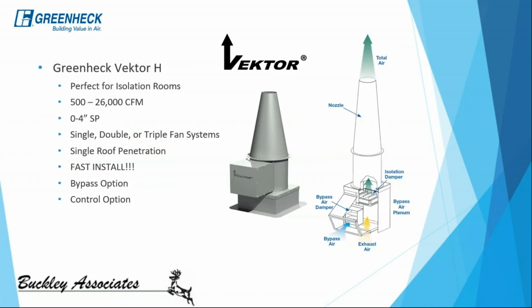So here's some quick information on our most commonly used laboratory exhaust fan. This is the Greenheck Vektor H. This fan is designed for anywhere between 500 and 26,000 CFM, and between 0 and 4 inches of static pressure. Up to 3 of these fans can be paired together into a single system, so we can put them all onto one box. What I mean to say is all these fans can be installed on a common exhaust plenum or box for additional capacity, or if you need some redundancy.